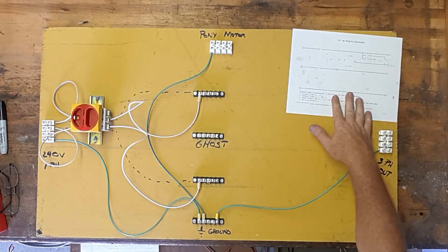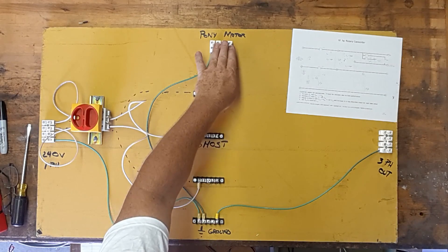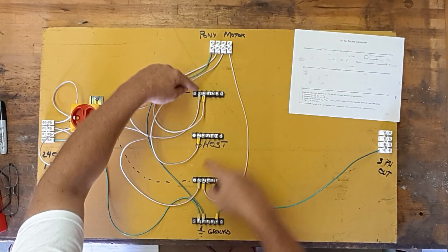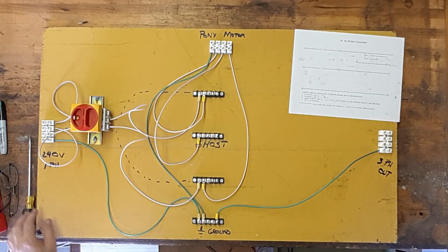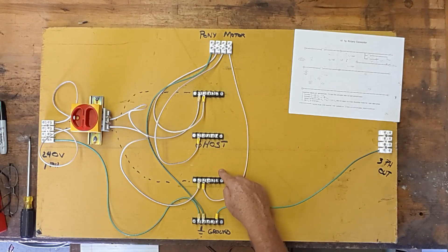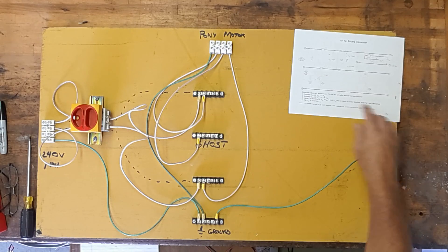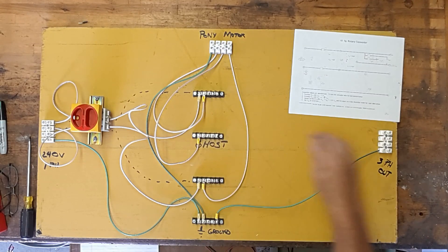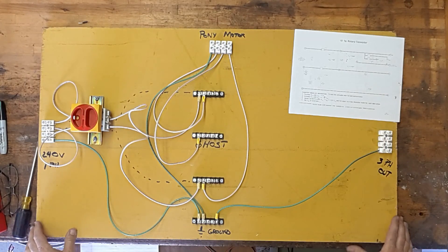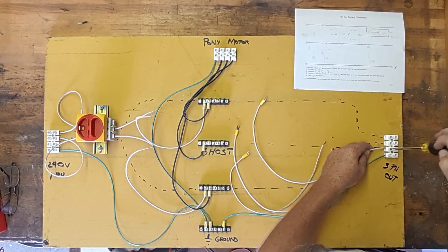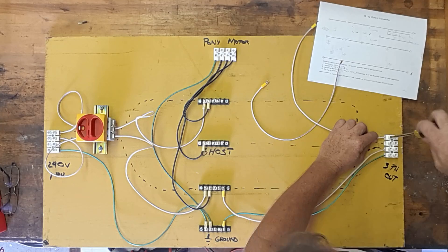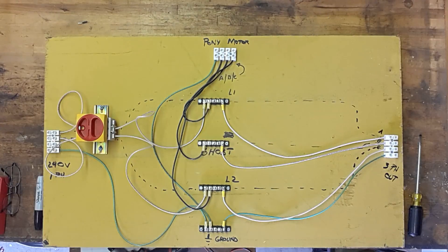And then I'm going to connect from my connector block to the switch. I've got my through line, 120, 120, making my 240 circuit. My ground line is here, and then my third leg is here. So you can see how that kind of lays out the same way. Okay. Now the next thing I'm going to do is connect the pony motor block down to here. Power coming in, switched, goes out to two legs. The pony motor is hooked to the two outside, and then the middle one here to the ghost leg. Next thing we're going to do is, these are our three phases. We're going to hook them to our output. And this is just a convenience thing. We can do whatever we need here. We can take measurements here. I'm using this because I want to be able to hook a motor up and try it based on this big layout board.